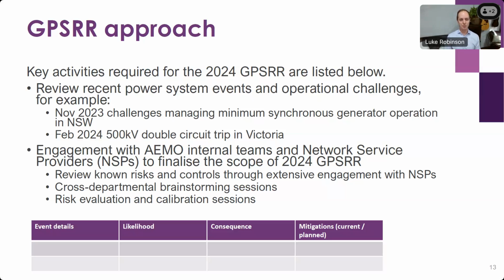We undertake cross-departmental brainstorming sessions to consider not just what do we know, what have we seen in the past, but what are the things that could arise in future. And then we evaluate the risks and calibrate those as well. The table here at the bottom of this slide, simplified for illustrative purposes, shows the type of information that we're collating here. It relates to the events, the likelihood and consequence of those events, and the mitigations, both current and planned. And this helps provide a systematic way of identifying the priority risks that we then might evaluate in greater detail through the general power system risk review. Naturally, we can't look at every double circuit fault or every triple circuit fault for that matter, or station trip. So we focus our efforts on those events and conditions that have the potential to lead to cascading failures or supply disruptions in the NEM.